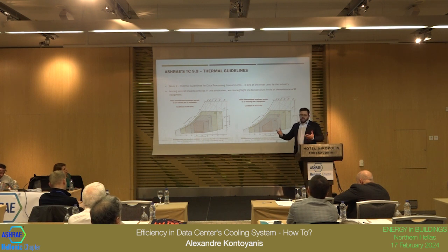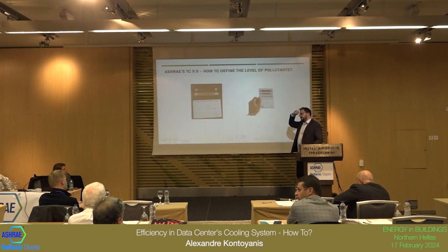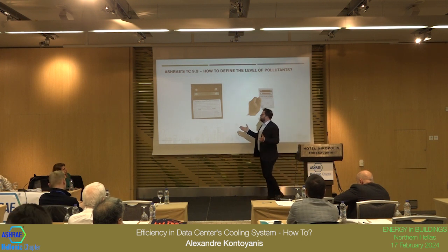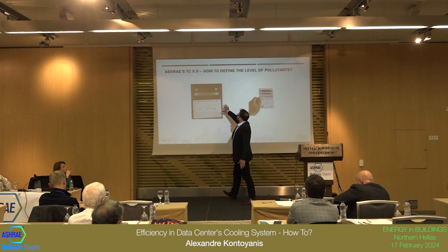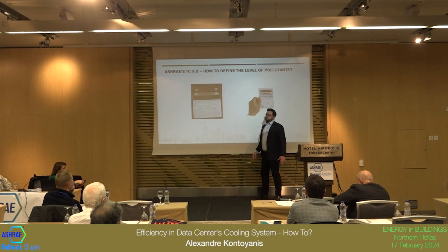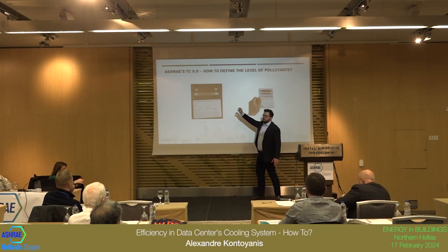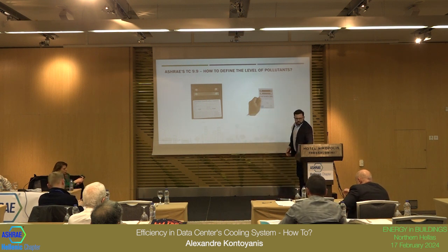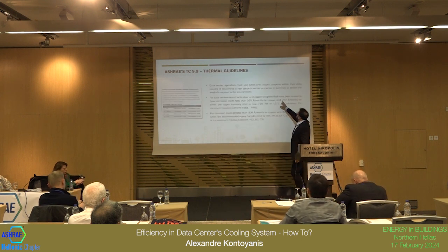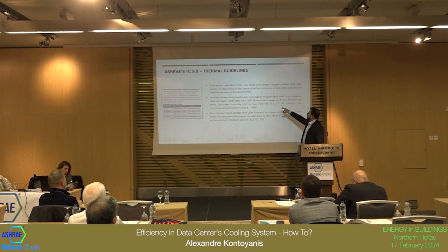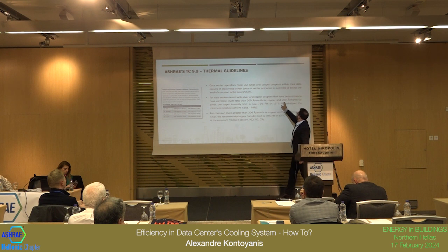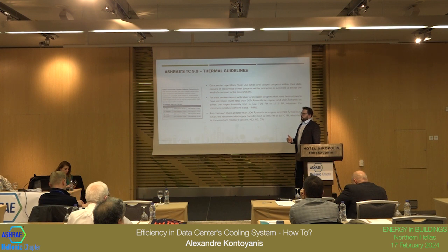What is low contamination and high contamination? How can I know? Testing. It's a cheap way to test. You expose copper and silver in an environment for 30 days, and you send it to a lab to calculate how much the corrosion was. And if the corrosion is more than 300 angstroms per month for copper and 200 for silver, you should drop your humidity limits. If it's less, you're fine.